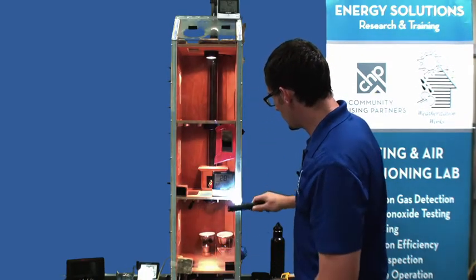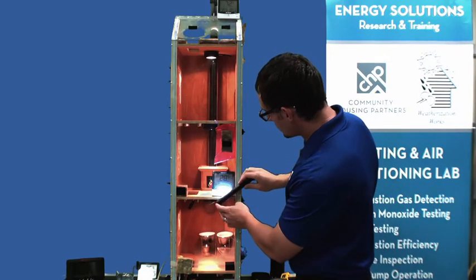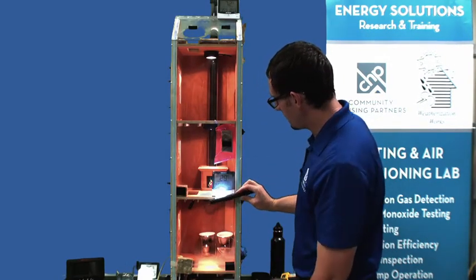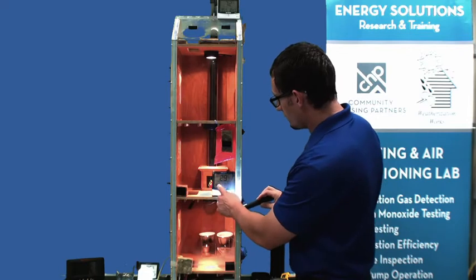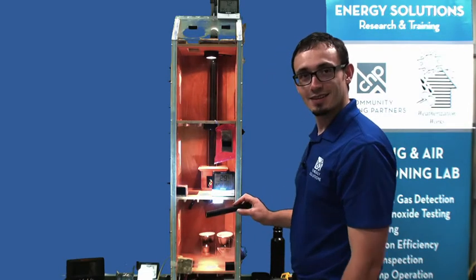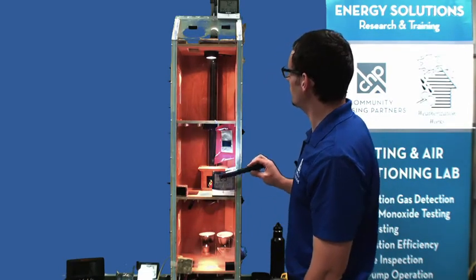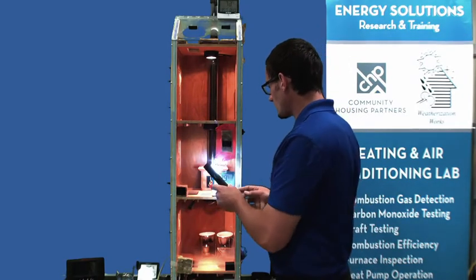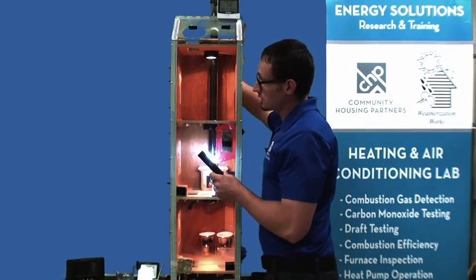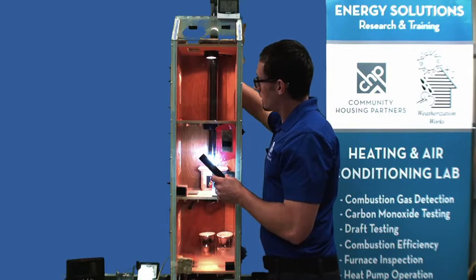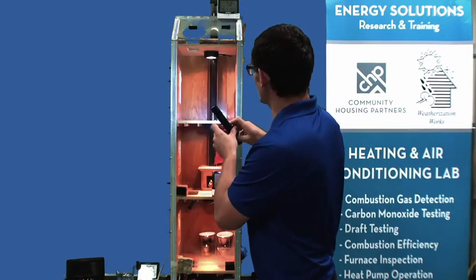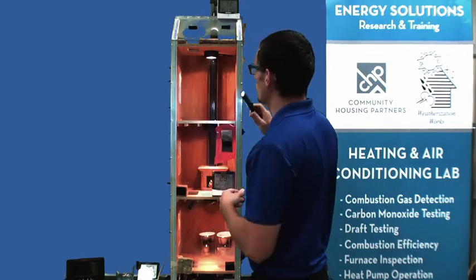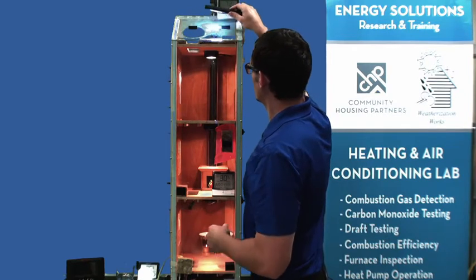29%, dew point's 103. We've already got moisture starting to show up on the second floor now. It's going to obstruct our view. Keep tracking up here. Nothing on the first floor, but I did try to get a little air movement. Let me see what's going on up here.